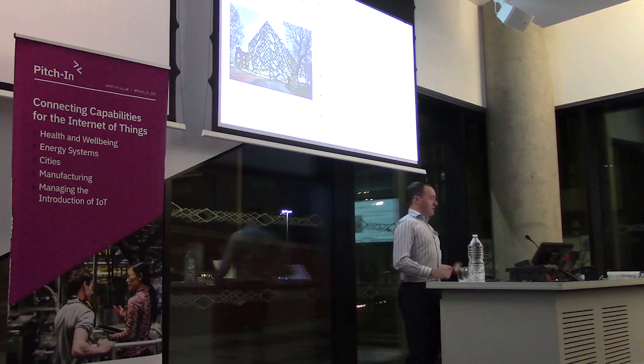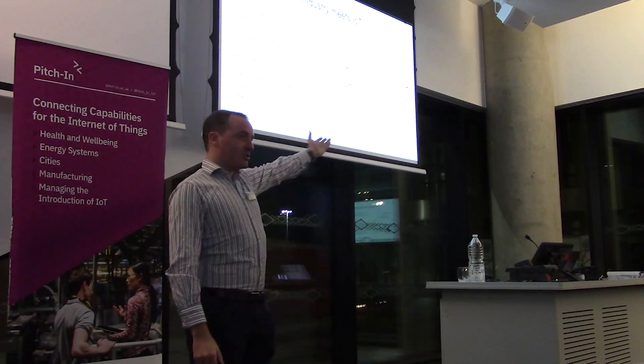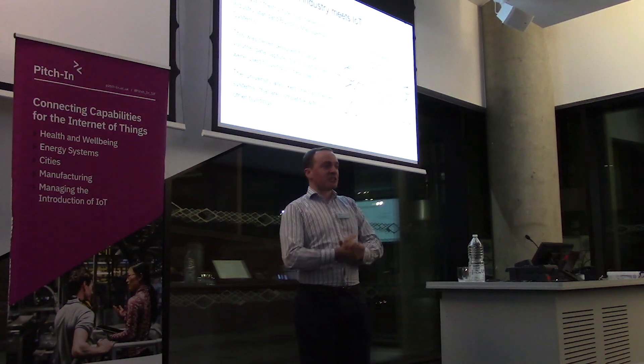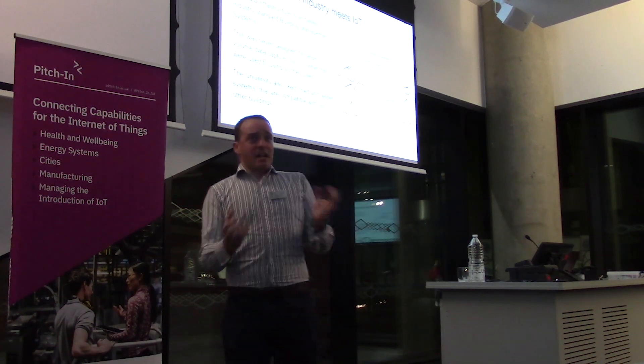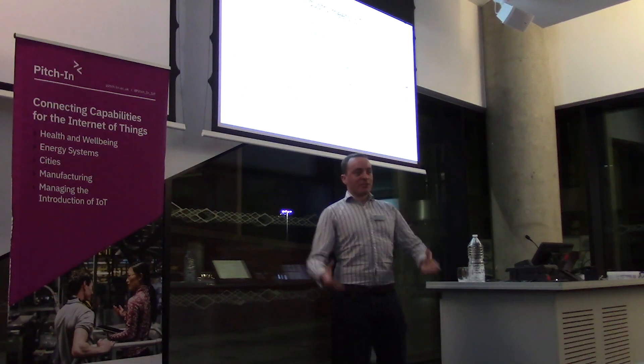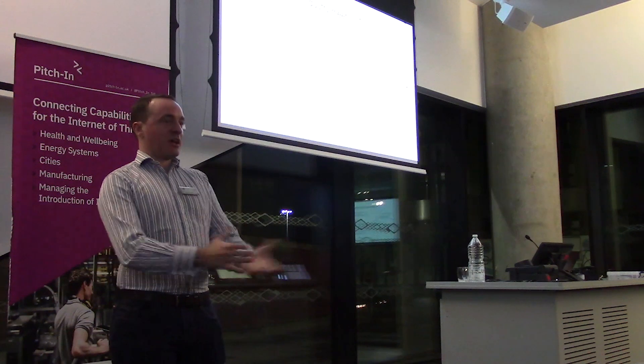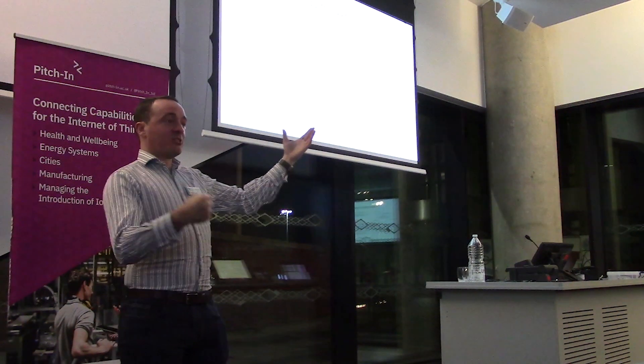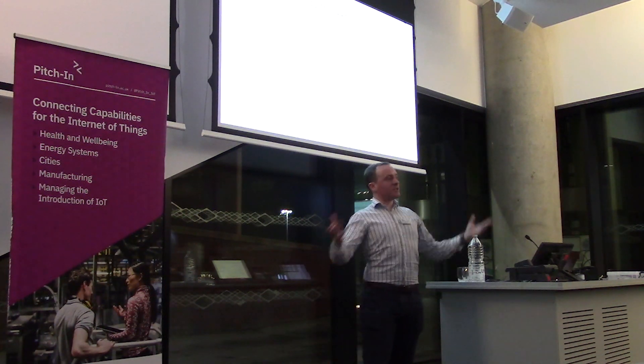Very much the vision was: let's have a smart building and it'll be brilliant. That crashed into the reality of the building industry — and the building industry is not evil. Pretty much, the building industry has subcontractors, and they have subcontractors, and they have subcontractors, and eventually you've got a guy whose job it is to pull cables. He's told we need loads of sensors, so he pulls a lot of cables and puts in a lot of sensors. But a lot of the technology they were using was just the standard building management system technology they've always used — it was really never designed to capture this volume of data at this rate. There are some fascinating weird problems in the building where the subcontractor chain was given a spec to put a sensor two metres above the floor in the atrium. Being an electrician, he used aluminium electricians' ducting — they solved the problem with what they had on hand, not necessarily what we, sitting in a wonderful IoT meetup, would have liked.